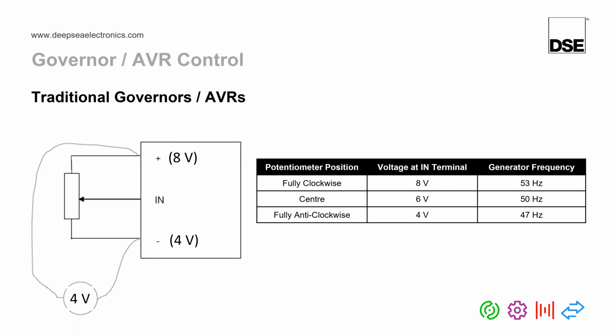So very typically, most governors will allow plus or minus 3 hertz adjustment, and AVRs will typically allow plus or minus 16% adjustment. These values do change from different governor manufacturers and different AVR manufacturers, but that's just a general rule. Plus or minus 3 hertz for governors, plus or minus 16% for AVRs.